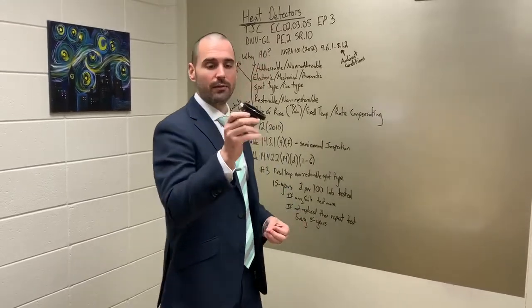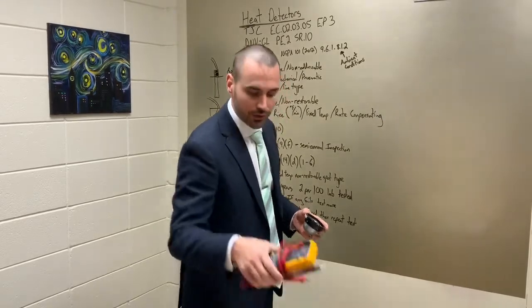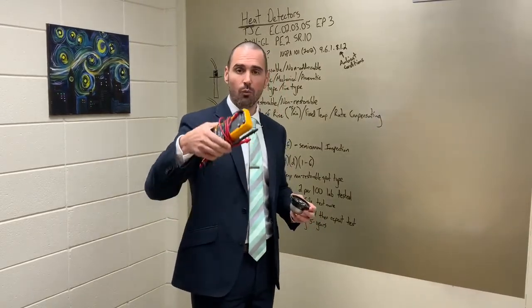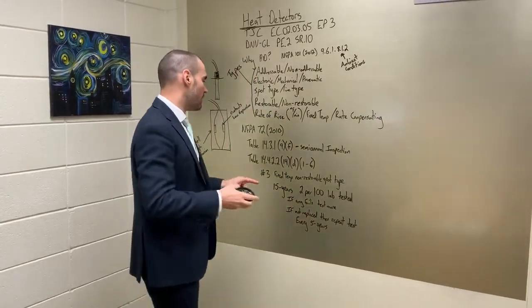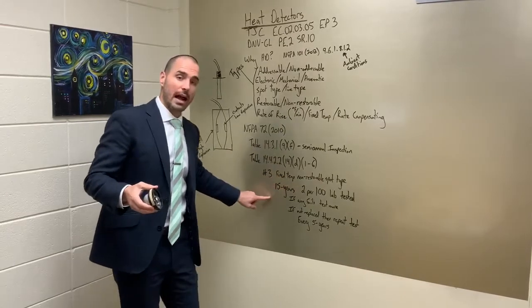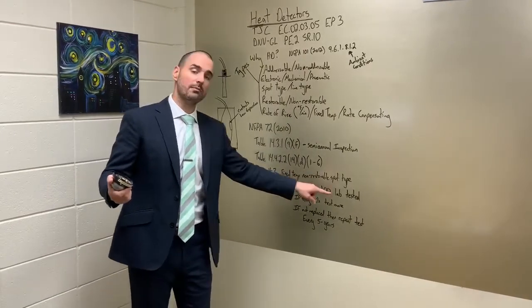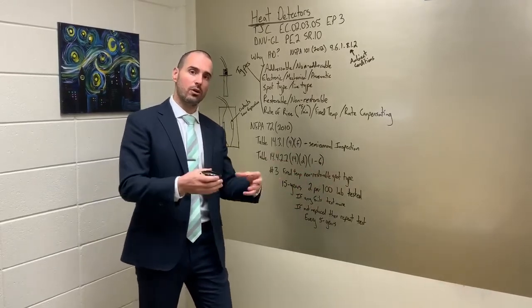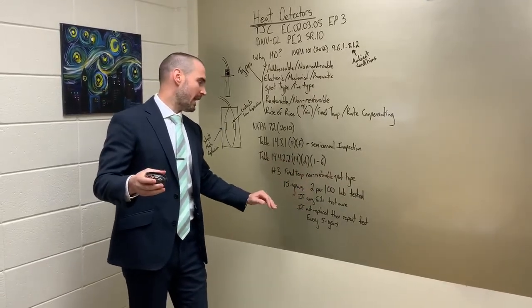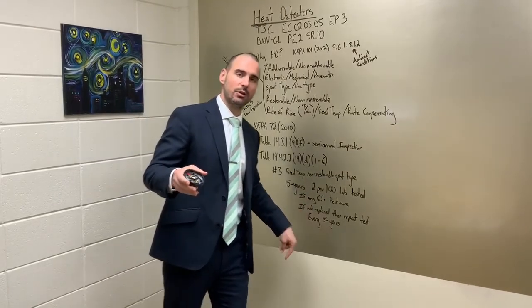If you go to the actual device manufacturer and look, most of the time what you have to do is you have to check and see what the resistance across it is. One more thing about these, fixed temp detectors, after 15 years after being put in service, you have to send them to a lab and be tested. If they fail, you have to test more to see if it's localized or global. And if you don't replace them, you have to retest every five years.